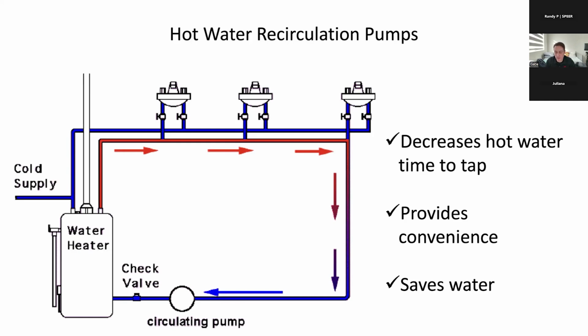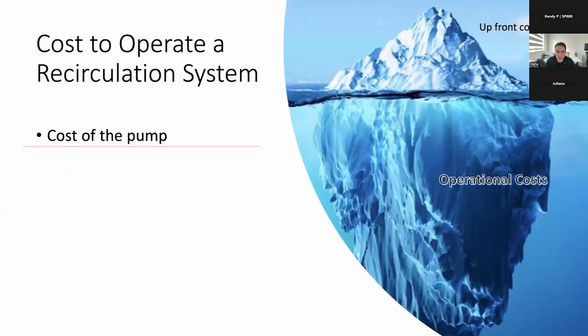So it's also going to have the effect of saving water. But alas, not all hot water circulation systems are created the same. So there's a cost to operate these systems. And so I often use this analogy of an iceberg where the tip of the iceberg is the upfront costs, but then you have all of the operational costs. So if the upfront costs are the costs of the pump and the cost of putting in a return line, the operational costs are the costs that you typically don't realize unless you're really focusing on your utility bills.